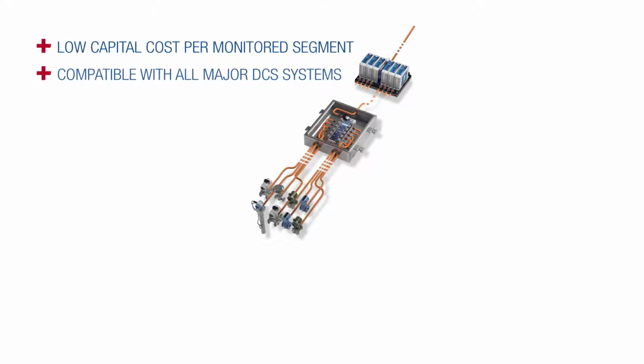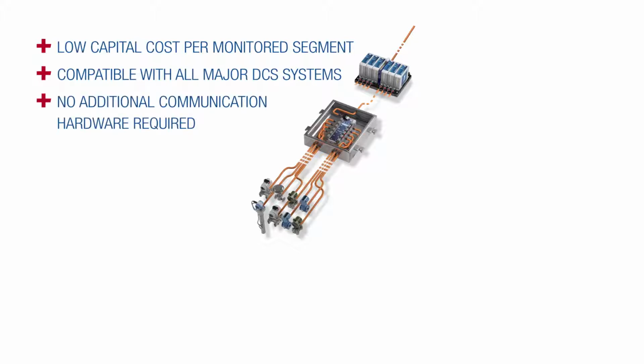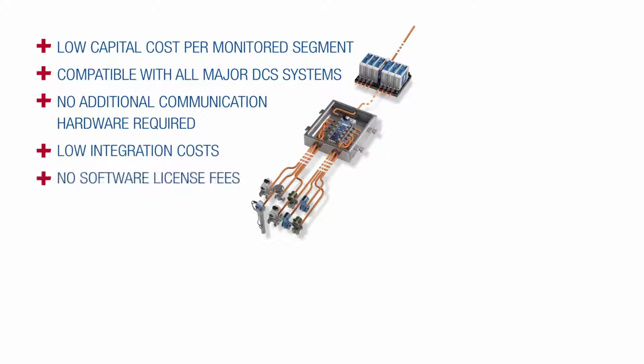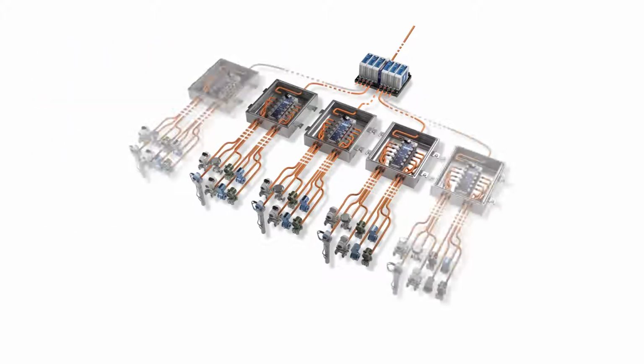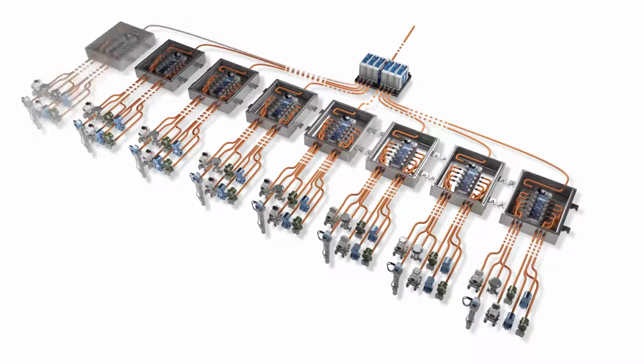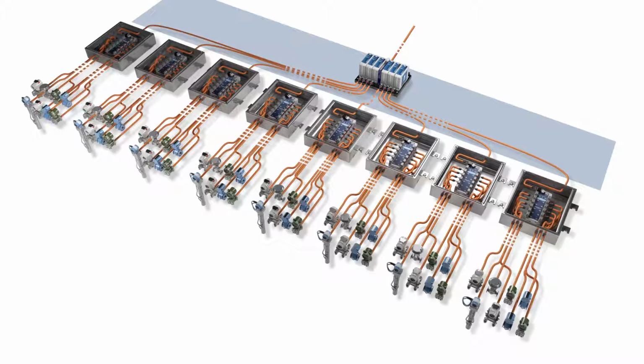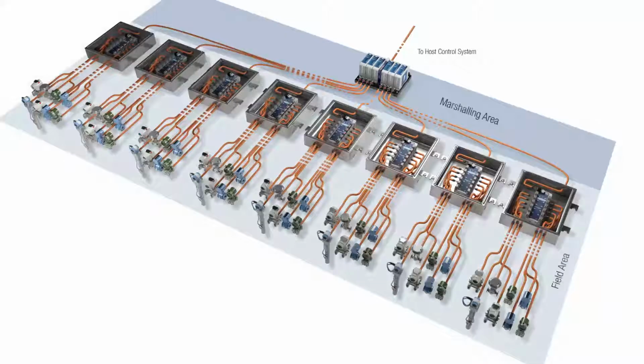Using this diagnostic product means for you low capital cost per monitored segment, compatibility with all major DCS systems, no additional communication hardware is required, low integration costs, no software license fees. It couldn't be simpler. Each F809F Plus diagnostic module enables you to monitor up to 8 segments simultaneously, driving down the capital cost per monitored segment.